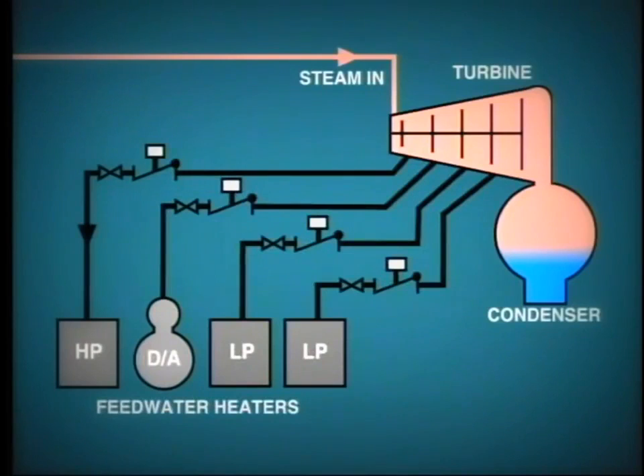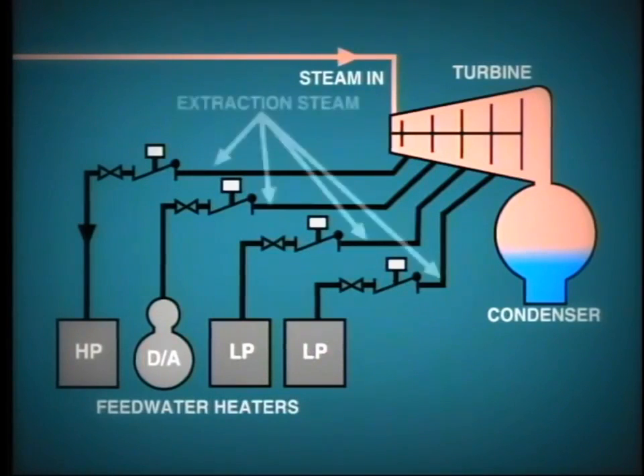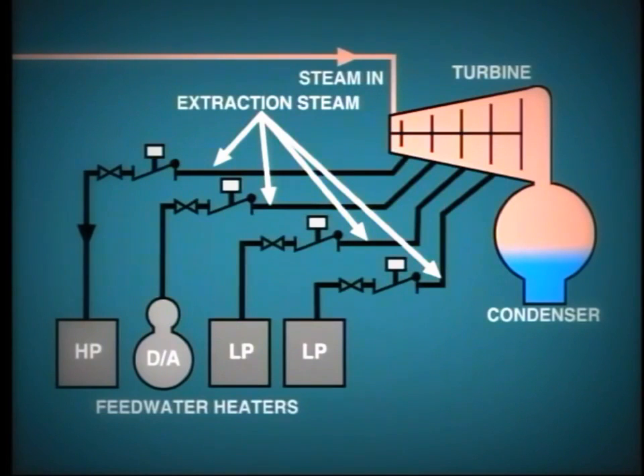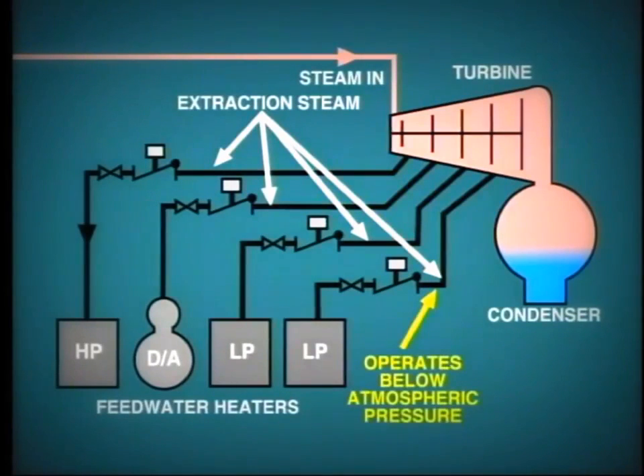Here is a simplified arrangement where we show just four stages of feedwater heating and therefore four extraction lines only. The extraction steam lines operate at much lower pressure than the main steam. In fact, in the case of a condensing turbine, the last stage of extraction will operate below atmospheric pressure.